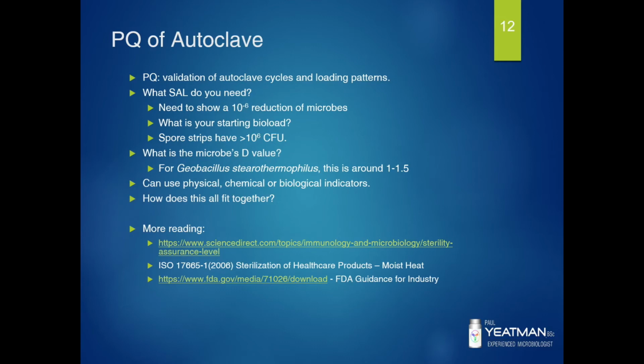Whereas with the loading pattern validation, you'd have a spore strip next to a thermocouple and show that for the validated time and temperature, that actually kills everything on the spore strip. So effectively shows you that you have a 10 to the 6 reduction.